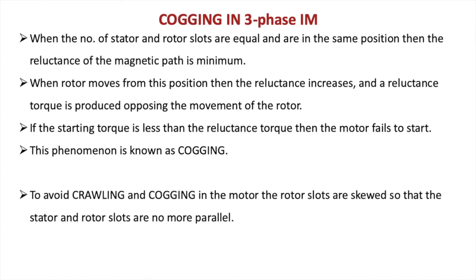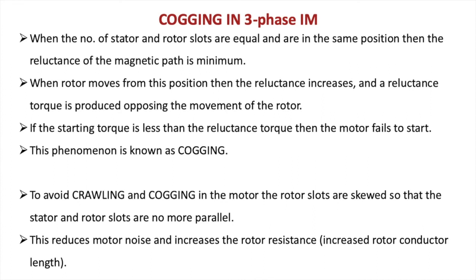To avoid crawling and cogging in the motor, the rotor slots are skewed so that the stator and the rotor slots are no longer parallel. That is, instead of having a straight slot in the rotor, if one end of the rotor is under the north pole, the other will be under some other condition, so the reluctance won't be the same at the two ends of the motor and cogging won't happen. Plus it will help in removing crawling also. This reduces the motor noise and increases the rotor resistance by increasing the length of the rotor conductor, because if you have a straight line, the length is less; if you have a slanting line, the length is more. So the increased length of the rotor conductors will increase its resistance, which helps in torque production.